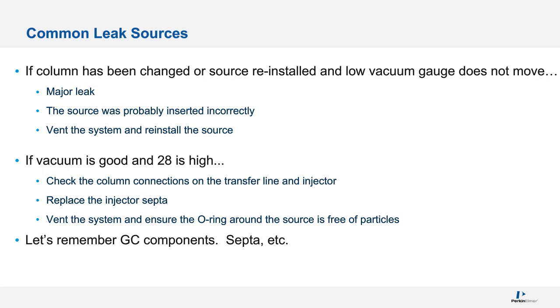You could have a hair or dust on the O-ring. I know some people wipe their O-ring with methanol. I typically don't do that, but just to make sure it's got no particles on it, because it is making the seal. That's what's nice about the dust off. You could squirt it right on the side of the source and know immediately if you have a leak there. That'll let you know immediately because it's right there at the source.